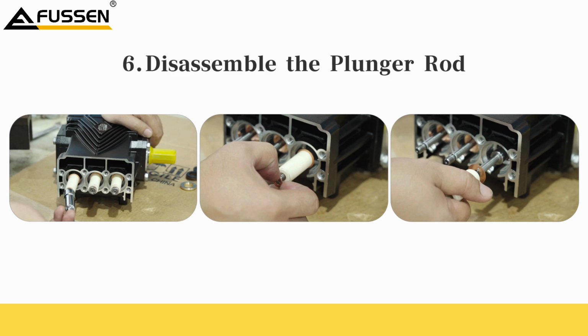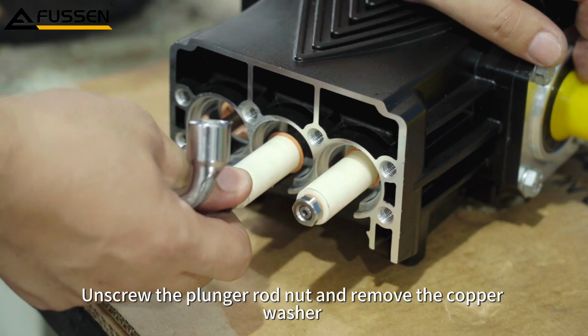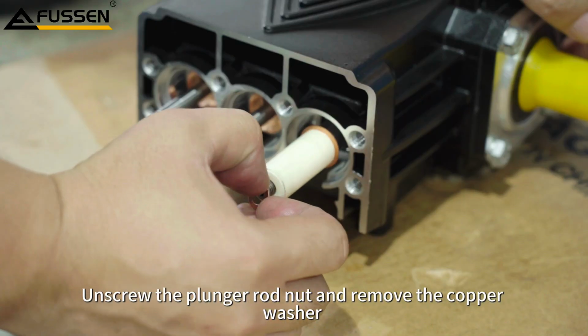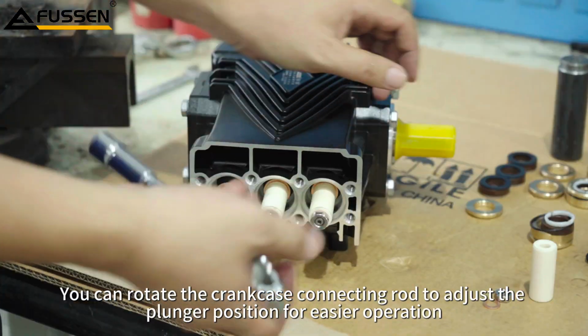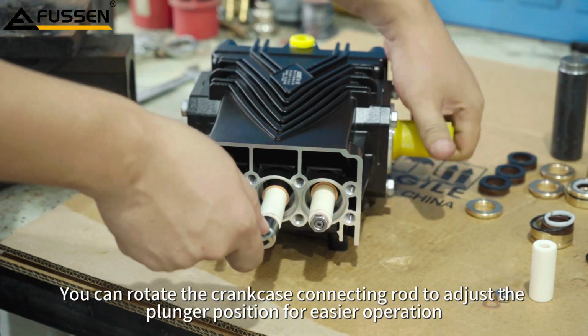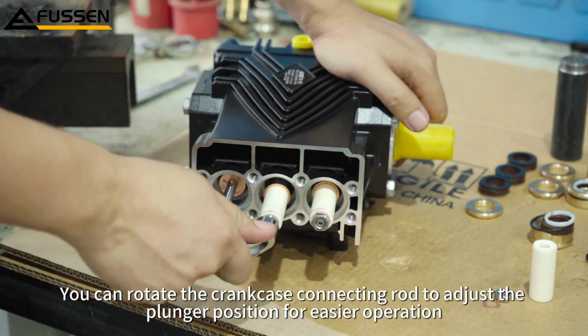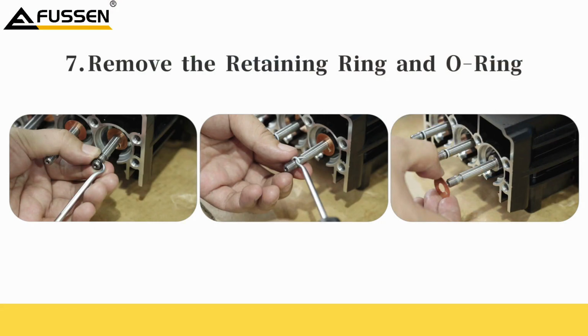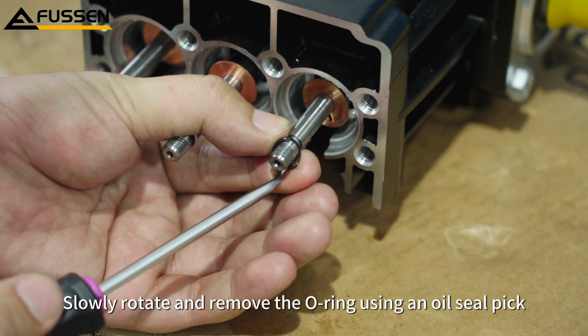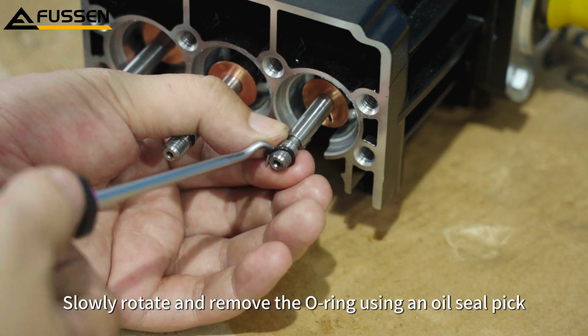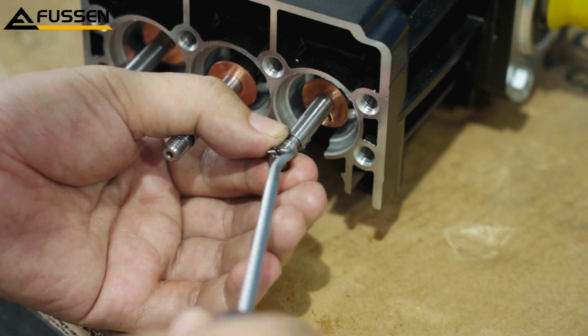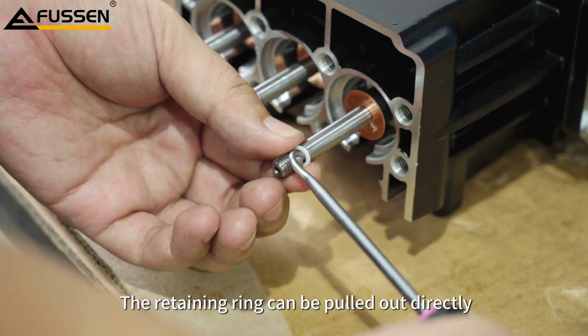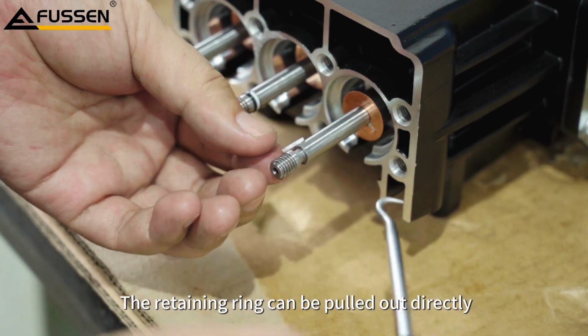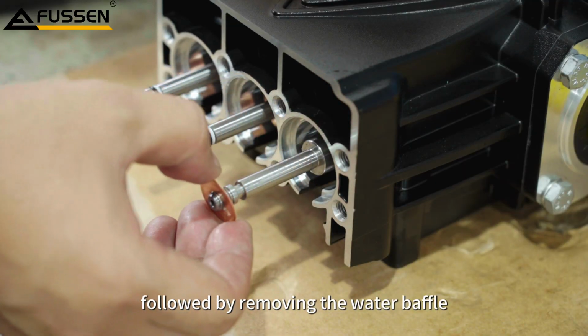Disassemble the plunger rod. Unscrew the plunger rod nut and remove the copper washer and ceramic sleeve. You can rotate the crankcase connecting rod to adjust the plunger position for easier operation. Remove the retaining ring and O-ring. Slowly rotate and remove the O-ring using an oil seal pick. The retaining ring can be pulled out directly, followed by removing the water baffle.